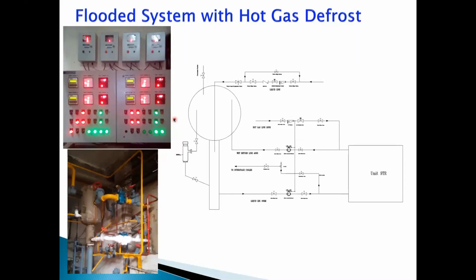Typically, you have a freezer which is operated for 2 to maybe 6 hours in a batch, twice in a day. So after 12 or 14 hours of operation, for the rest of the 10 hours the freezer is not operational. It might get defrosted because there is no further refrigerant coming in and the doors are kept open. The frost will melt and the water may get drained. But when you have a cold storage running 24 hours, 365 days, you can't afford to switch it off. So the alternative system available was using water. There were water sprinklers provided on top of the coil.